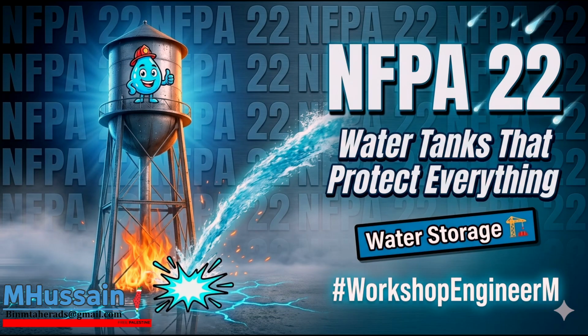A cistern isn't actively feeding a fixed fire pump inside a building. Right. It is a static pool of water designed specifically for municipal fire department apparatus, the fire trucks, to pull up, drop a hose, and draft from. It is the ultimate interface point between private infrastructure and public first responders. To facilitate this interface, the standard requires a dry hydrant assembly, which is essentially a hard suction pipe that reaches down to the bottom of the tank and comes up to the surface with a connection manifold.